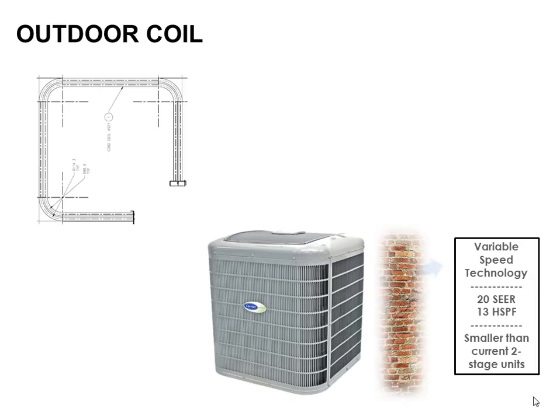All right, a couple other things on this guy. A couple reasons why this guy is so much more efficient. One is that the condenser coil is much larger than it used to be. I shouldn't call it a condenser coil, right? I should call it an outdoor coil. Instead of having the coil on 3 sides like a traditional unit has and having the 4th side as an access panel, this guy actually has coil surface area on all 4 sides, and the corner of the unit is actually the access, as well as accessing it through the top through the condenser fan section. So from the service standpoint, that's less than ideal, but from an efficiency standpoint, it gave us a huge amount of surface area, which allows us to be much more efficient.